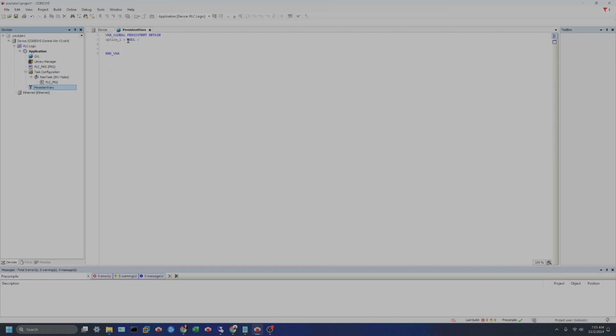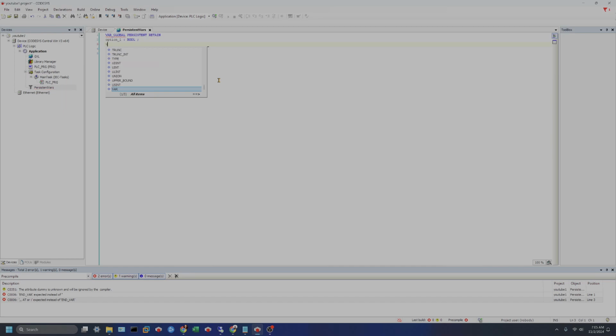You want to be careful of that, because if you have, let's say, a VFD position and you were wanting to save the last version of that, if you're constantly writing to this, you can damage your PLC and burn it up. So you don't really want to do that, or put sliders or things like that in there.